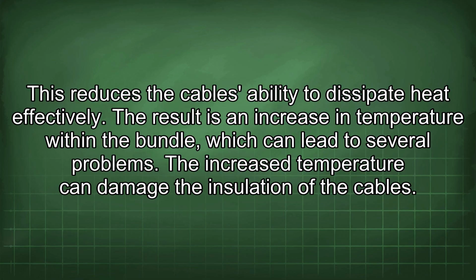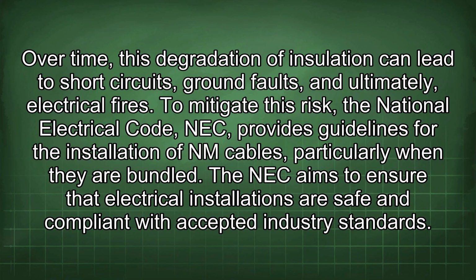The increased temperature can damage the insulation of the cables. Over time, this degradation of insulation can lead to short circuits, ground faults, and ultimately, electrical fires. To mitigate this risk, the National Electrical Code (NEC) provides guidelines for the installation of NM cables, particularly when they are bundled. The NEC aims to ensure that electrical installations are safe and compliant with accepted industry standards.